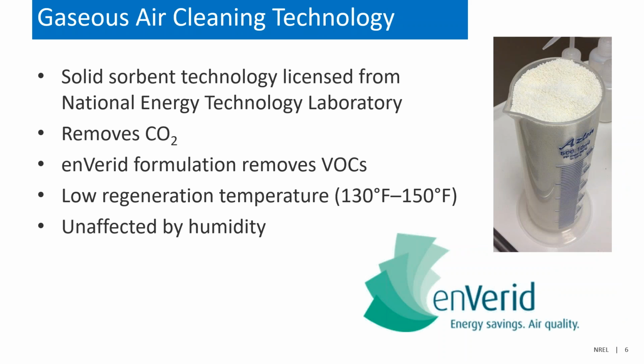All right, so the technology that we're going to discuss today was developed by enVerid, and they licensed this solid sorbent technology from the National Energy Technology Laboratory, or NETL, and it absorbs CO2 from the air. And then they developed their own formulation that removes volatile organic compounds, including formaldehyde and aldehyde and so on. The advantage of this particular sorbent material is that it has a low regeneration temperature between 130 and 150 degrees Fahrenheit, and it's unaffected by humidity levels.